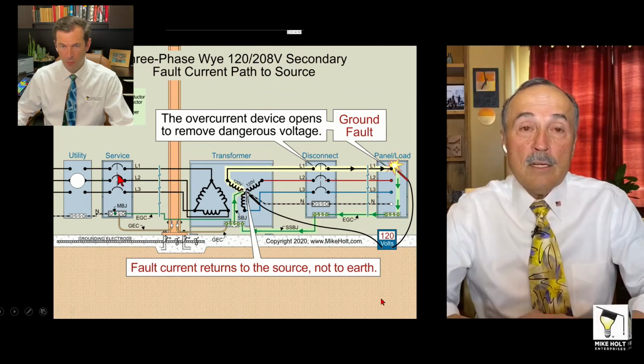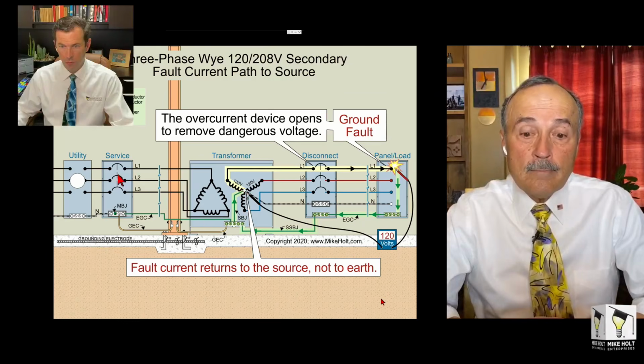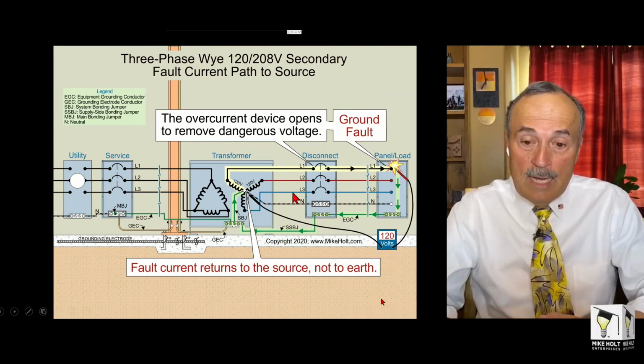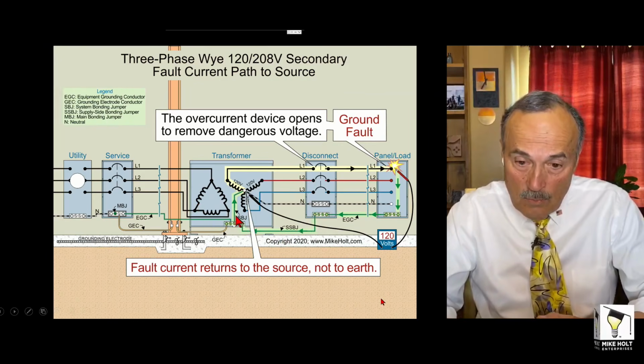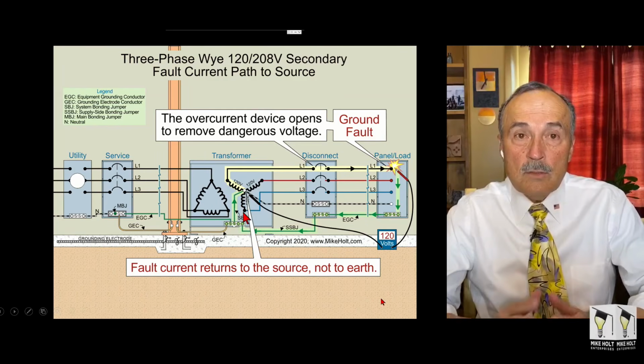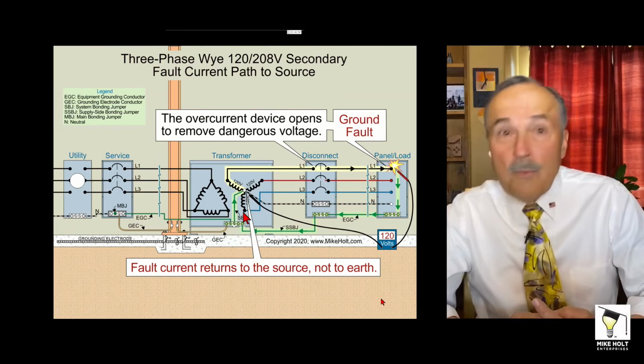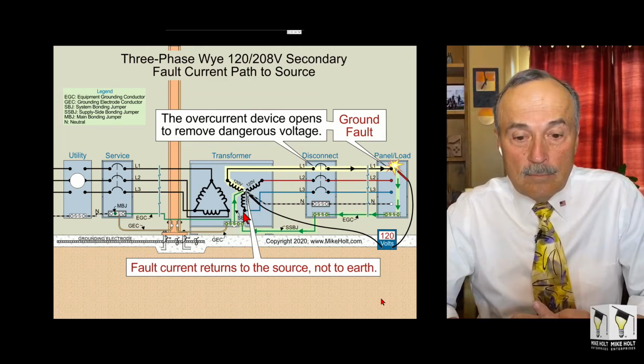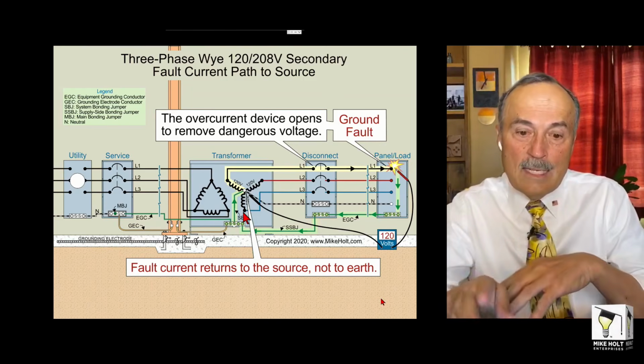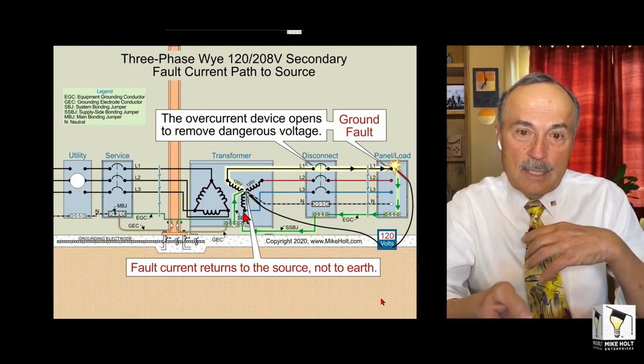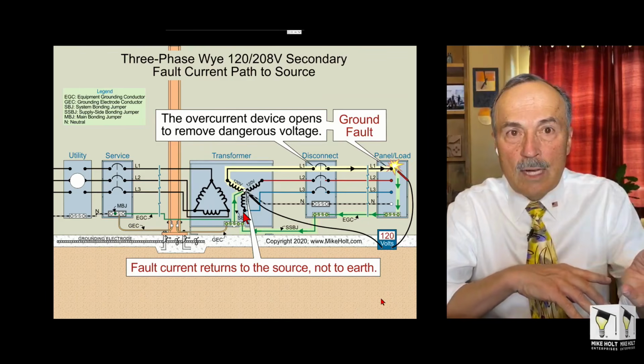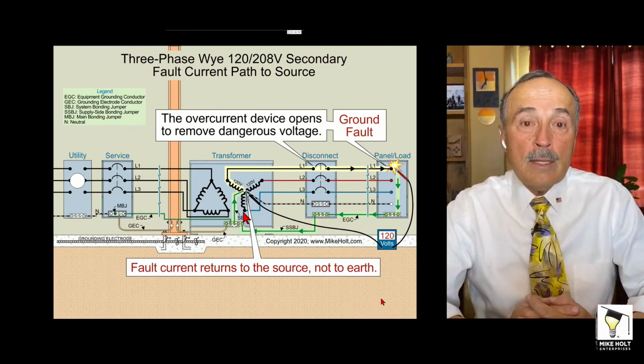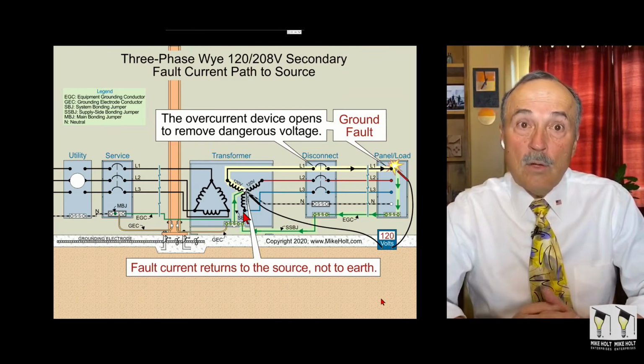and maybe you clear the primary because it's on the supply side. So that's why you have a supply side bonding jumper. Probably it'll clear the primary side, because it's one winding on the secondary side, but then that current travels on the primary side of 3 windings. So I'm just going to say that's what it will do. I don't know if it's going to clear it or not. It probably will.